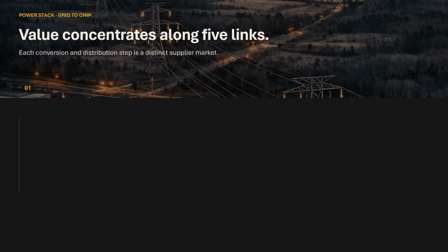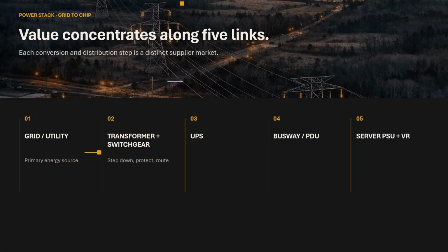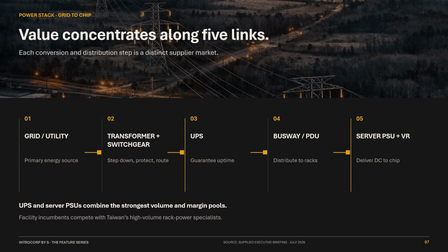Power reaches the chip through 5 distinct links. It begins with the utility, moves through transformers and switchgear, passes into uninterruptible power systems, travels across busway and PDUs, and finally reaches server power supplies and voltage regulation. Each step has its own engineering requirements and supplier landscape.